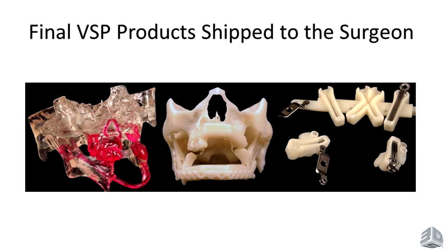We print the models overnight using stereolithography — everything the laser touches hardens, everything else stays liquid. The part drops 0.1 to 0.15 millimeters and repeats thousands of times until you have a three-dimensional model. It then runs through post-processing so it can be shipped as a medical device with instructions for use on how to clean, sterilize, and use it in the operating room. We've done thousands of these — fibula free flap reconstructions of the jaw or craniofacial area — all 3D printed medical devices with cleared 510(k)s.